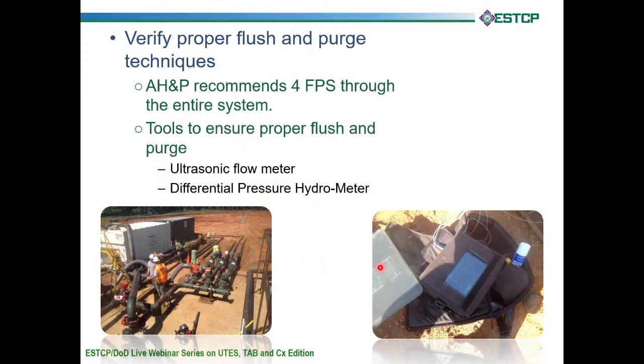On this particular project, we used our ultrasonic flow meter a lot. We actually went to every single one of those submains and made sure we had 4 feet per second. We made sure we had 4 feet per second through the larger pipe, all the way back, every different pipe size. In this particular picture, we have a frac tank over here, which is just an open loop tank.